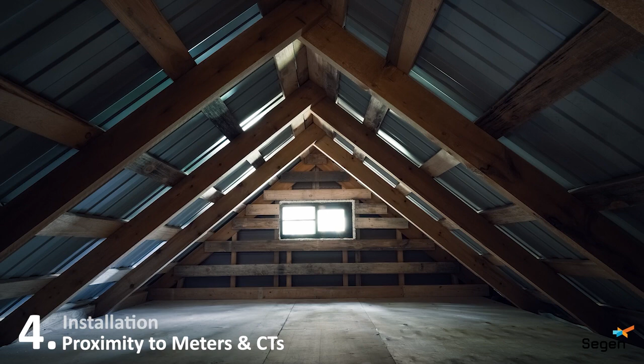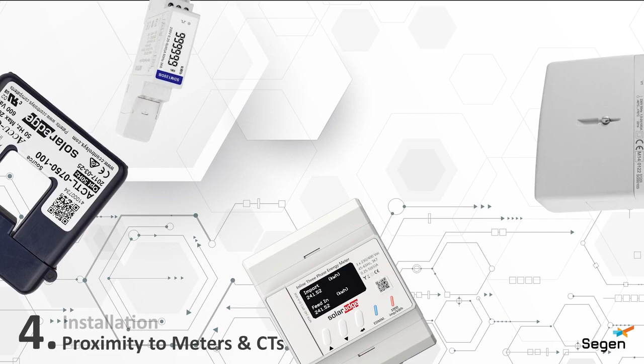It's also important to consider if the installation location is in line with any meters or current transformers which may need to be installed. Most storage solutions use a meter or CT to detect when energy is being exported, with a view to directing energy to the batteries. These meters, or CTs, will be installed on the incoming grid supply and may need to be within a certain proximity to the charge controller.